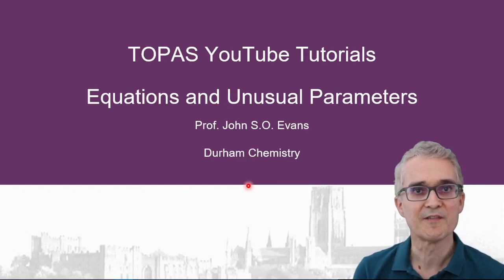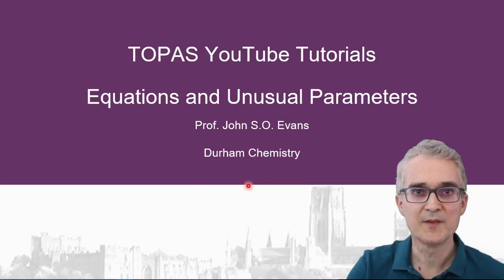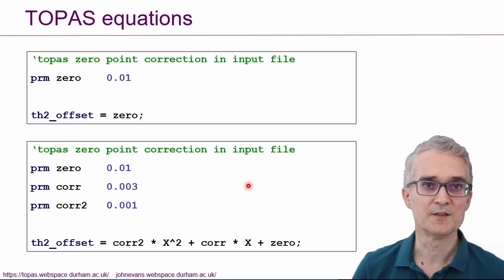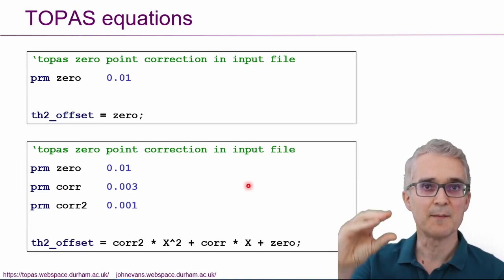Or perhaps even to refine some rather unusual parameters from powder diffraction data. So I want to pick up from the yttrium oxide example that we looked at in one of the earlier videos. You might remember from that video that one of the parameters we were refining was a zero-point correction for the diffractometer to describe the offset between the true 2θ value of the diffractometer and the setpoint of the detector.